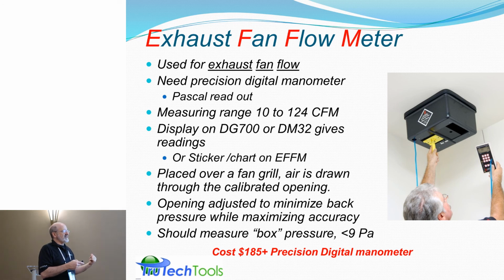You do need a precision digital manometer to get the Pascal readout, and the measurement range is 10 to 124 CFM on exhaust only or return only. You go out of that and there's too much box pressure and it won't work. It doesn't function. The digital manometers we patched around before have those calculations built into them, or there's actually a sticker on the side of it.